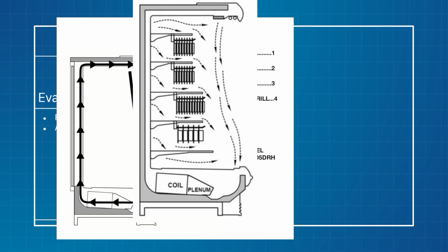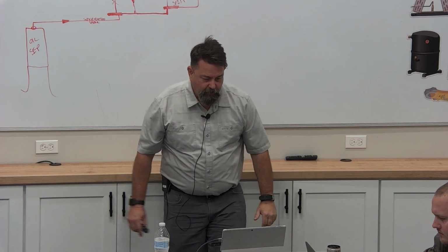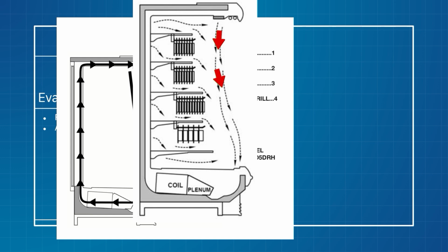So let's talk about shelves for a minute. Shelves play a massive factor in how this works. Now, you can see my air curtain's not a straight line after all. It's got a little wave in it. This is a case where everything is working properly. This is what it looks like. So what's going on with my waves? Why is this not a straight line?